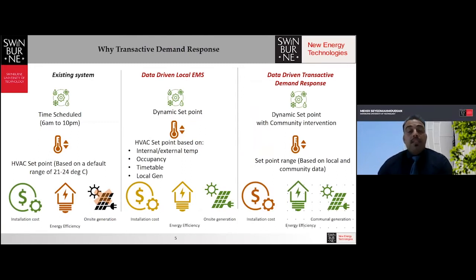So we came up with two approaches, two stages of the energy management system. The first was the data-driven local energy management system, based on more than 11 parameters identified as affecting HVAC operation in a general building. For institutional buildings specifically, these include internal and external temperature, occupancy rate — since, unlike many commercial buildings, our occupancy rates vary a lot during the day based on the timetable — plus the timetable itself and local generation. Based on this, we wanted to prioritize our HVAC operating points and set points.